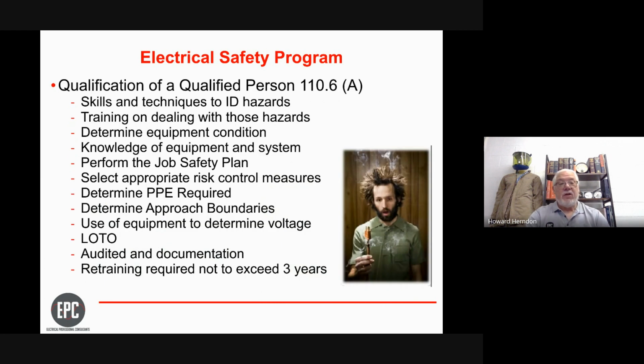Some qualifications of qualified personnel: identify electrical hazards, have training to deal with those hazards, and determine the equipment condition — knowing the difference between a piece of equipment that's good to work on and one that isn't. Knowledge of the equipment and the system is needed, along with the planning piece regarding risk controls, PPE, boundaries, and lockout tagout. Also, what type of equipment to use to determine voltage, with retraining required not to exceed 3 years.